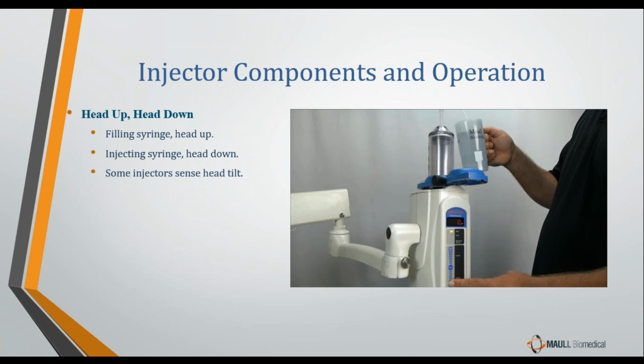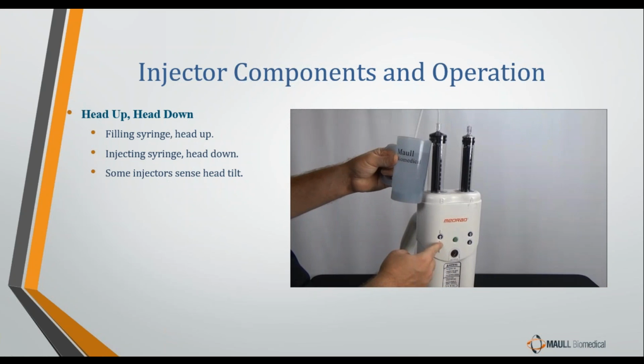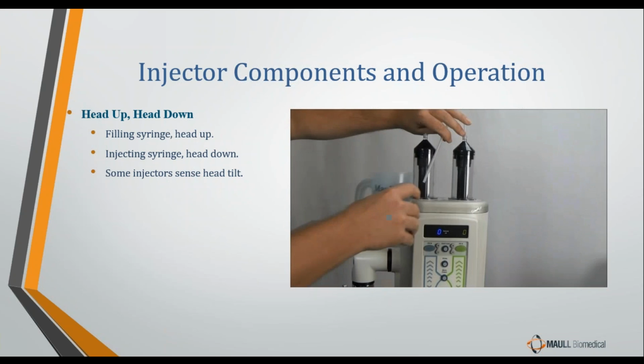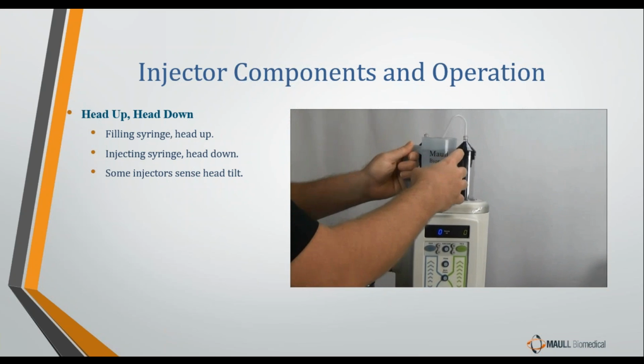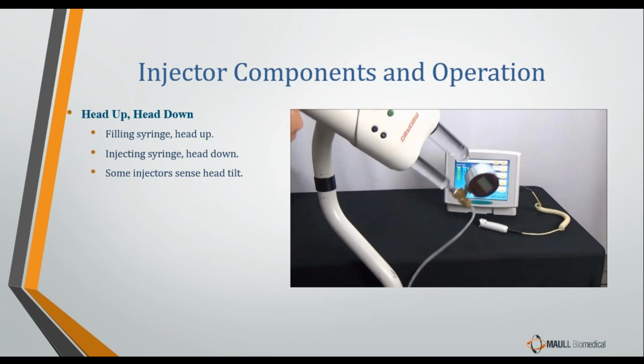All right. Now, when we're filling the syringe, this is something that the operators know, and this is something that the maintenance personnel need to know as well, because this does come into play when we're doing PMs and pressure checks and things like that. And this also lends itself to one of the common problems with a lot of the contrast injectors that pop up relatively frequently. Whenever we are filling the syringe, or the operator is filling the syringe, the injector head is always tilted up. The reason for this is, when we fill the syringe, air will get in the syringe. So the last thing we're going to do before we go firing it is purge the air out. So the injector head needs to be tilted up to get any air out when we prime it.